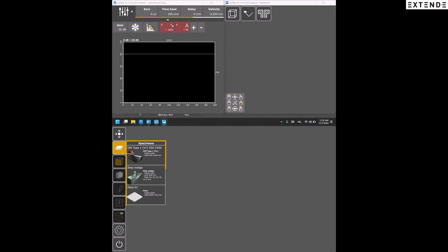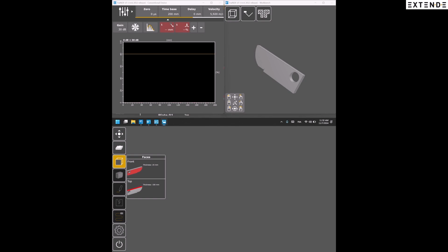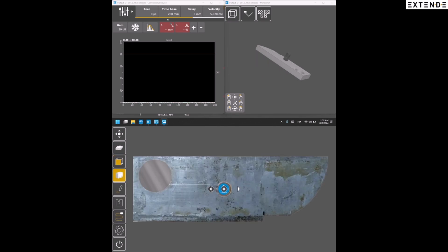This exercise includes a V1-block, a step block with flat bottom holes, and a steel plate to inspect. In the Specimen menu, select the V1 calibration block, and in the Faces menu, select the 25 mm thick front face of this block. By opening the Probe menu in the menu bar, you can select the probe for your inspection. In this exercise, only a 4 MHz dual-element straight beam probe is available. Scan the dummy straight probe on the front face of the V1 block displayed in the digital mockup.